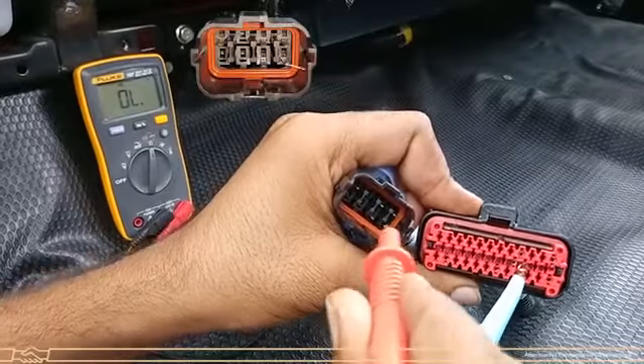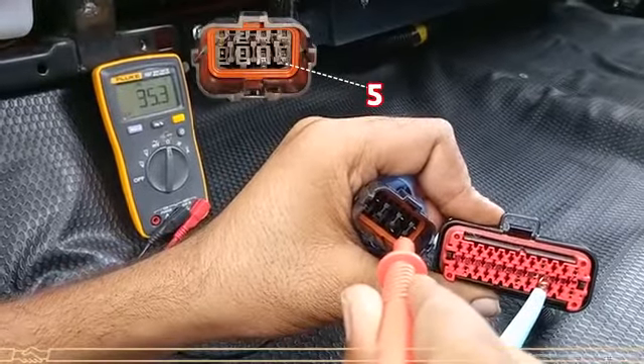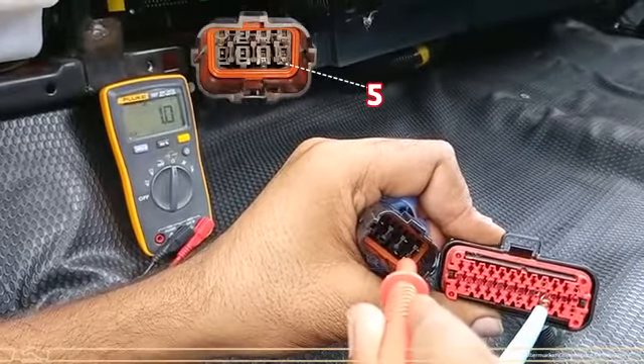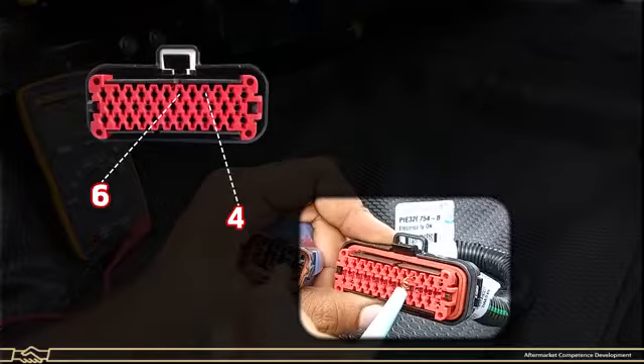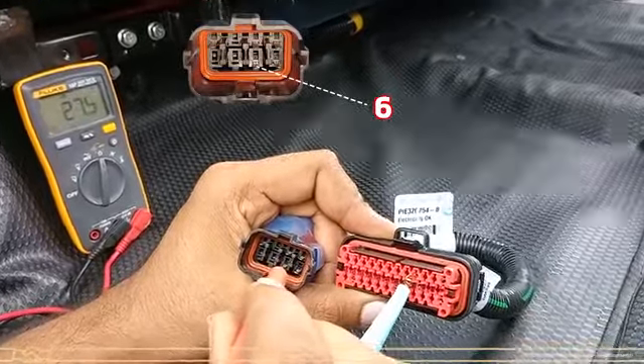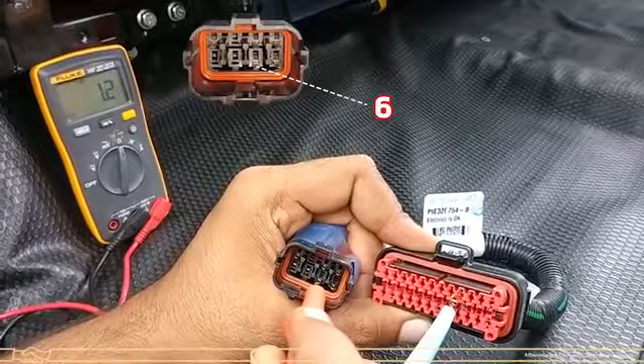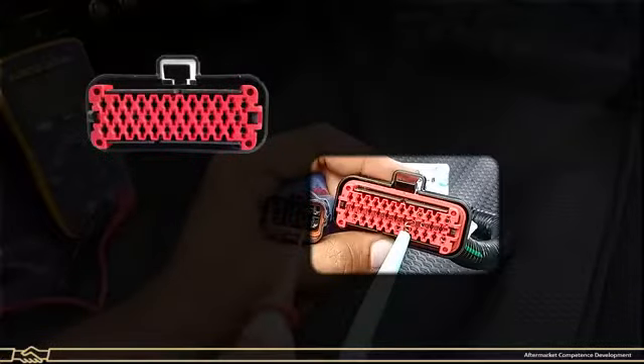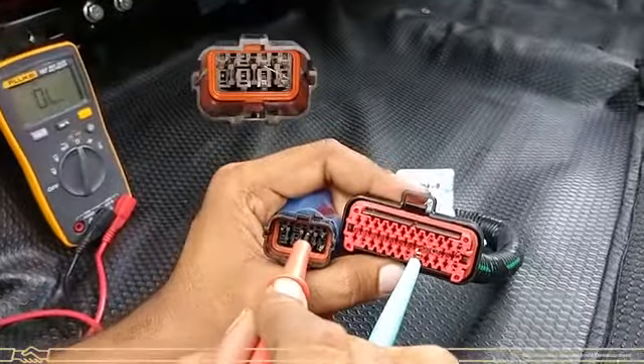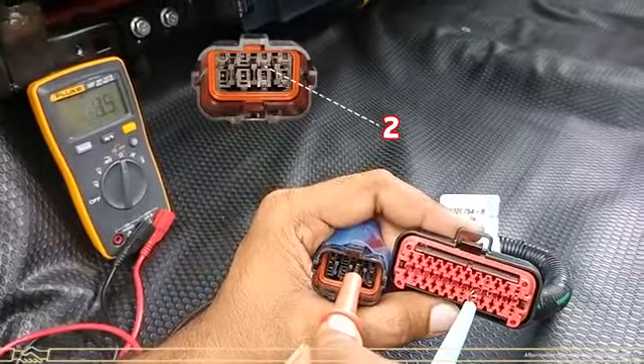Check continuity between pin 15 of 35-pin connector to pin 5 of 5-pin connector. Check continuity between pin 4 and pin 6 of 35-pin connector and pin 6 of 5-pin connector. Check continuity between pin 14 and pin 16 of 35-pin connector to pin 2 of 5-pin connector.